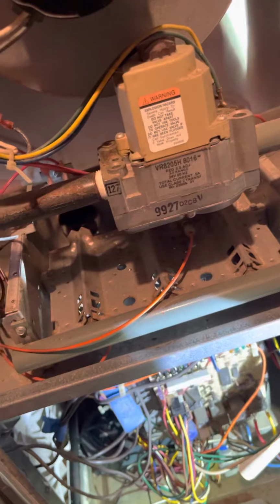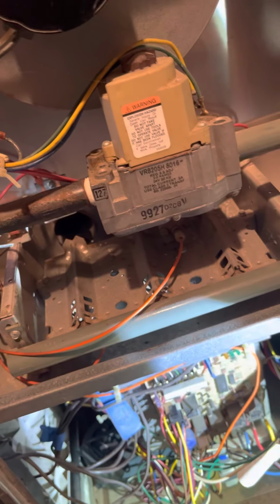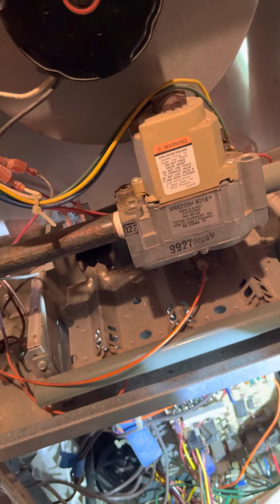So here we go. This is a sequence of operation. We're gonna get inducer, and then we're gonna get pressure switch. So I'm gonna come right over here, and I'm touching the pressure switch. You can hear the inducer come on, and the light's not on. There we have a light.